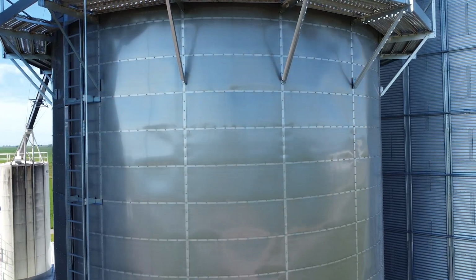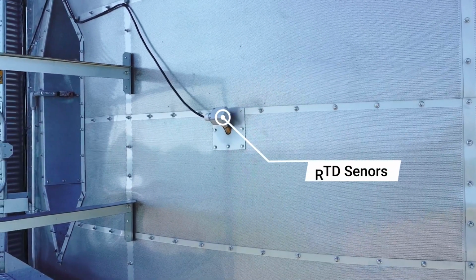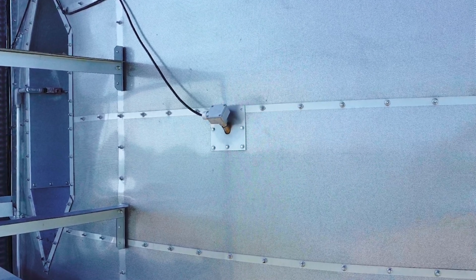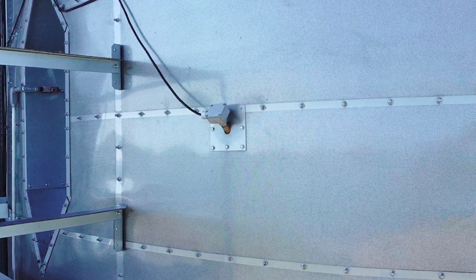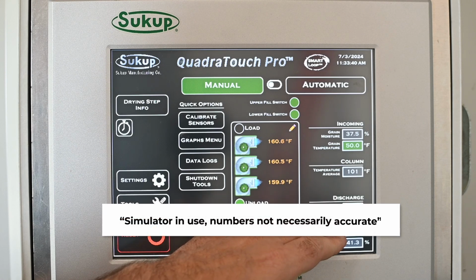Then as we come down the dryer, we'll see, in this case, one of the grain column RTD sensors. There's actually 4 of those spread out top to bottom and around the dryer, and it gives us a very good average of all the grain temperature inside the dryer. This will be displayed as column temp on the touchscreen.